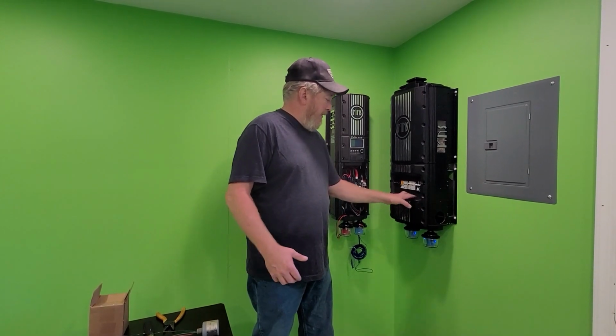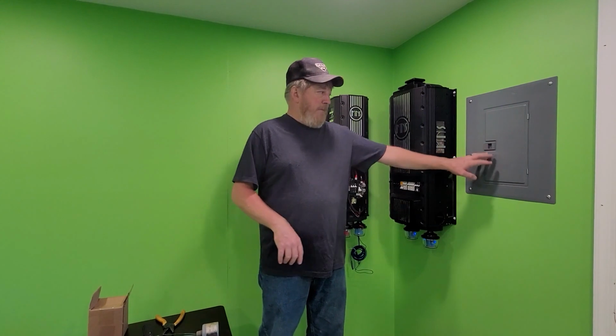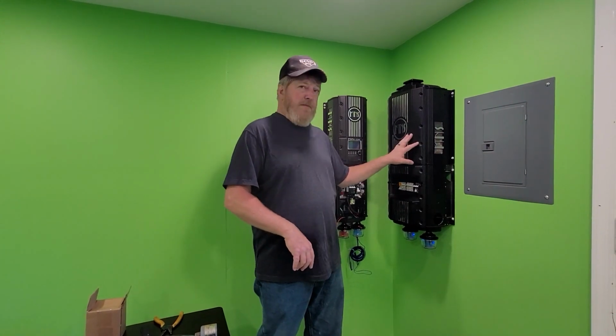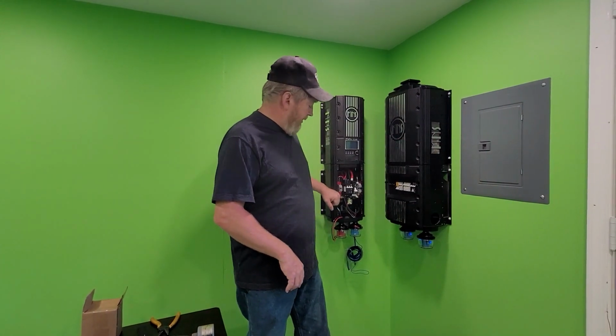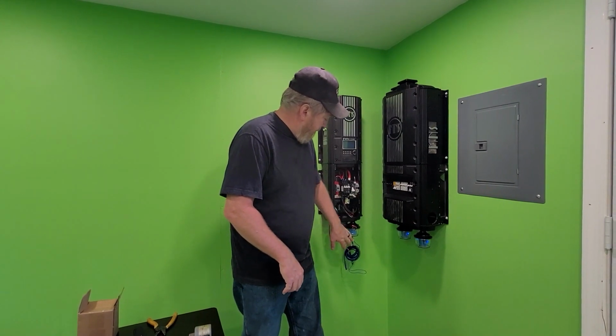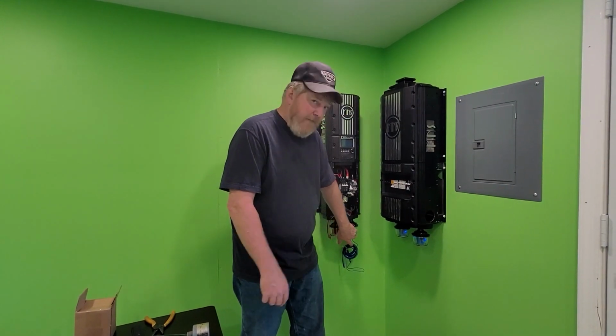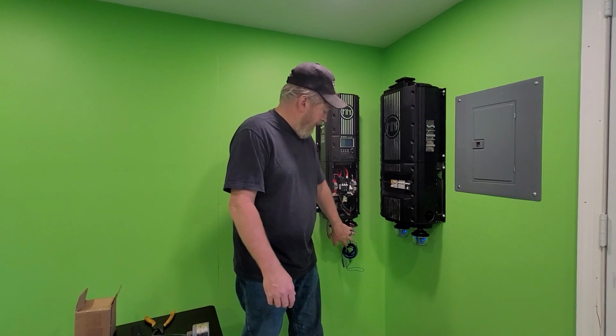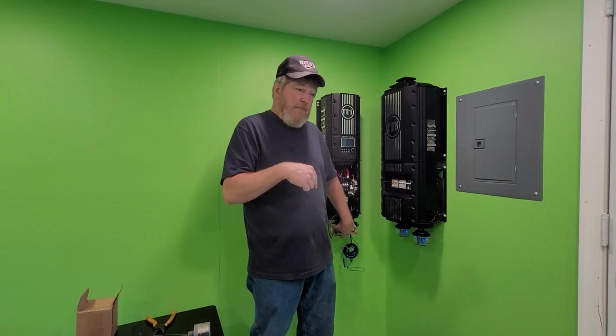So that's kind of my rule of thumb, I put them anywhere where it makes sense - every breaker panel, every input and output of an expensive inverter, every charge controller. This one has a Midnite SPD 115 on it for the DC side because we're using lithium batteries.